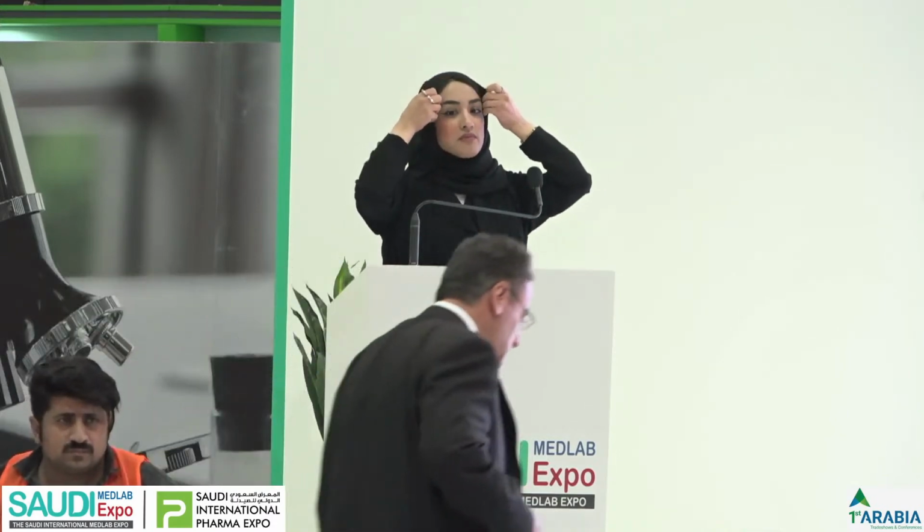Thank you to all the speakers for a valuable presentation today. My question is for Dr. Ma'in and Ms. Siham regarding the QC. Sometimes we have conditions where we repeat the QC multiple times, and it still gives us an outlier result. We did more justification regarding changing the QC, but we still have outliers. Is calibration the next step we should do to solve this issue?